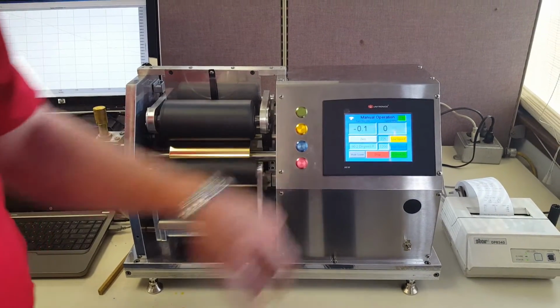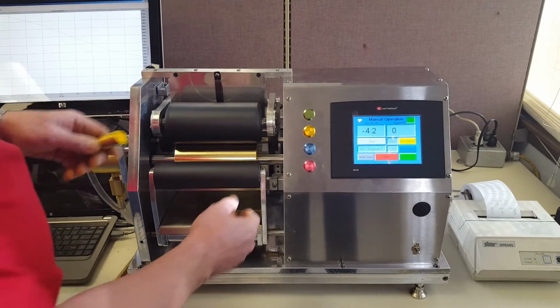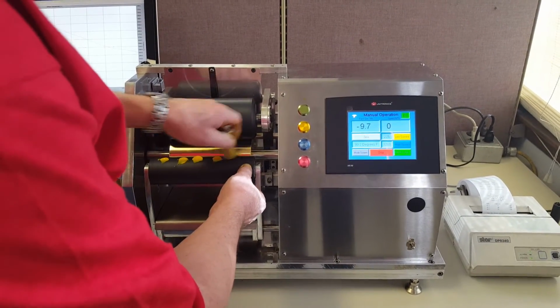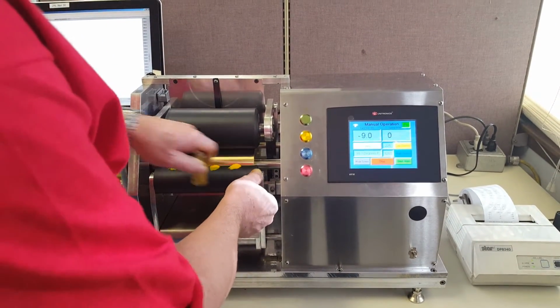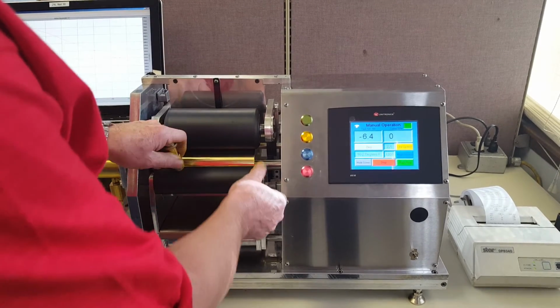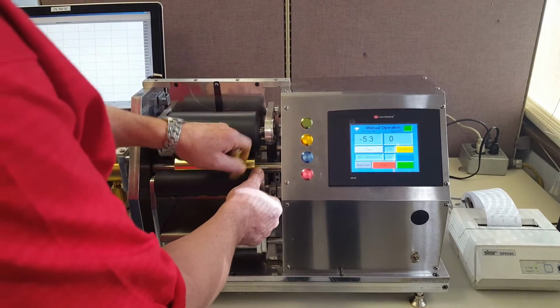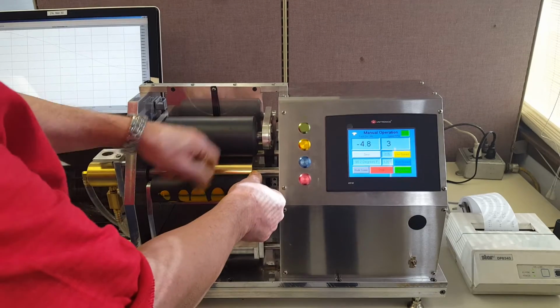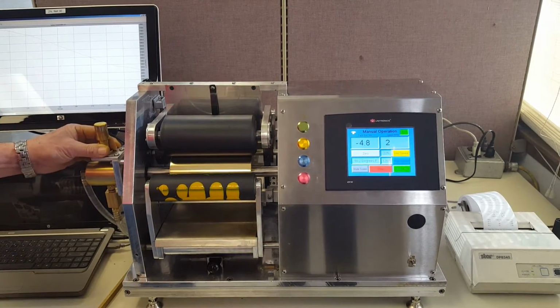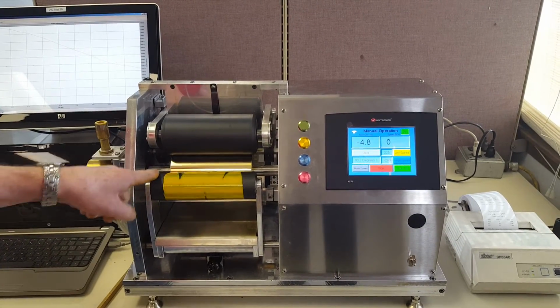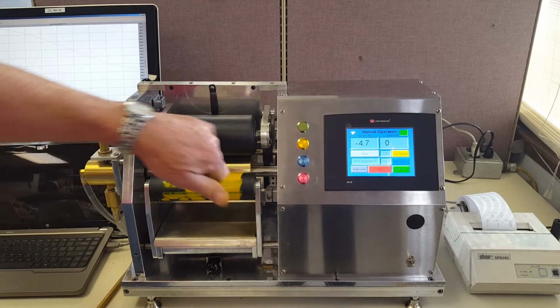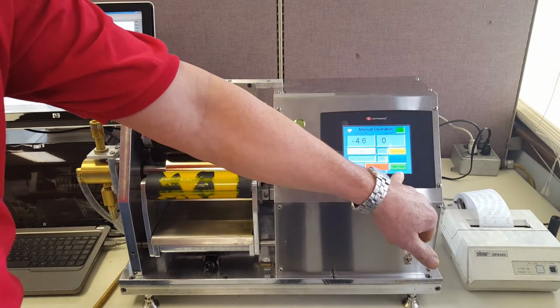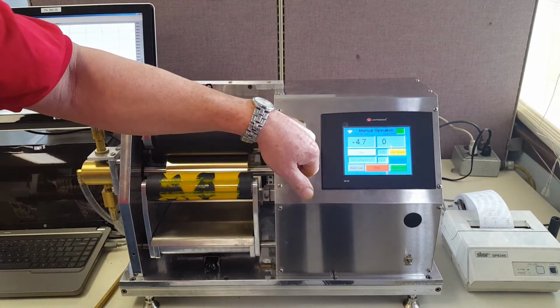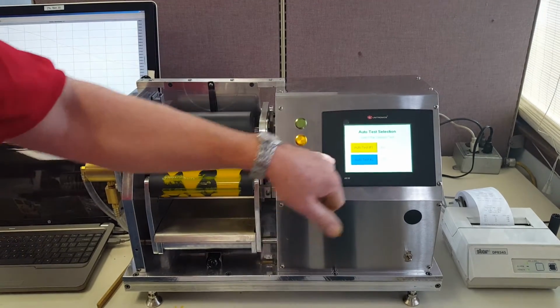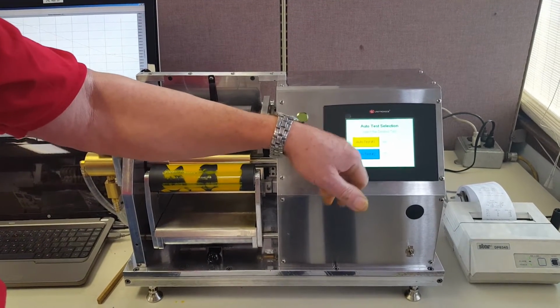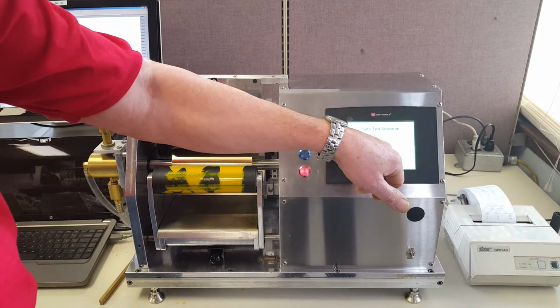I'm going to turn off the rolls and apply the ink as we normally would. Notice I'm only putting the ink on a distributor roll, not the top roll, because that's relatively delicate. Once I have the ink on the roll, I'll give that a little turn. Now I'll either press the green start icon or the green button. It's going to ask which auto test I want to use since I have more than one - I'll select number 1.